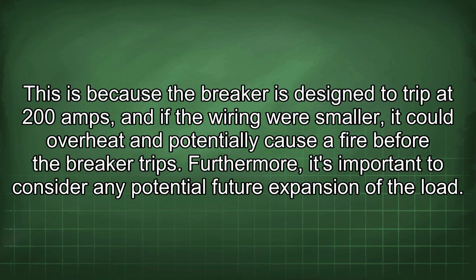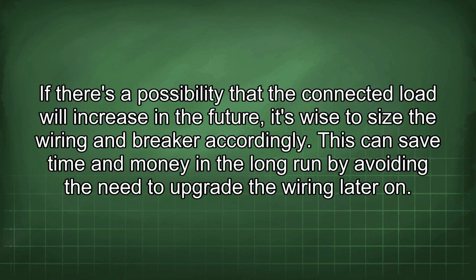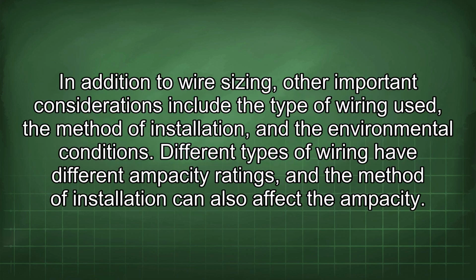Furthermore, it's important to consider any potential future expansion of the load. If there's a possibility that the connected load will increase in the future, it's wise to size the wiring and breaker accordingly. This can save time and money in the long run by avoiding the need to upgrade the wiring later on.